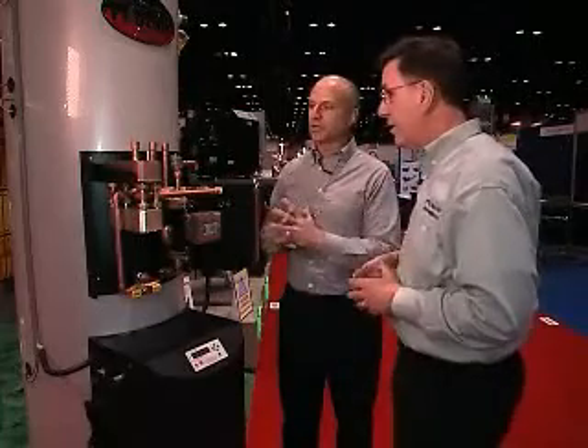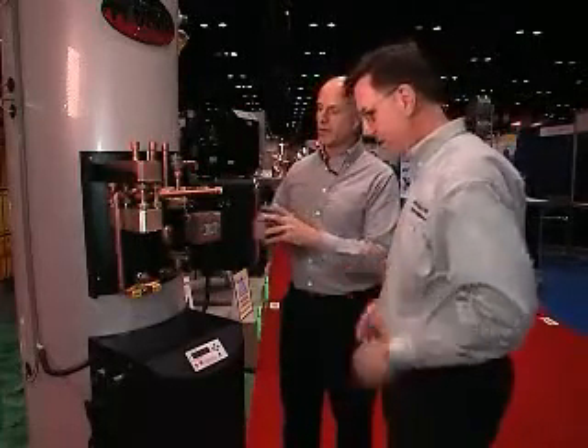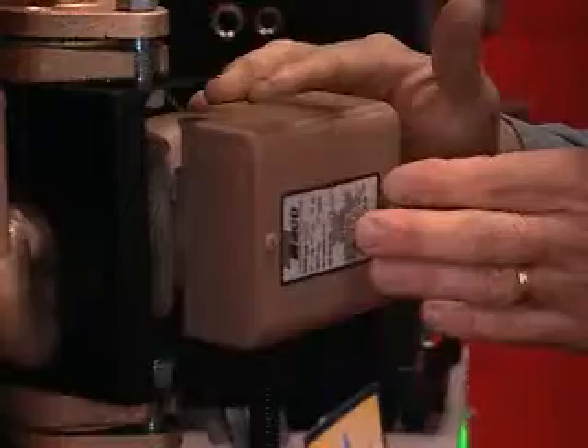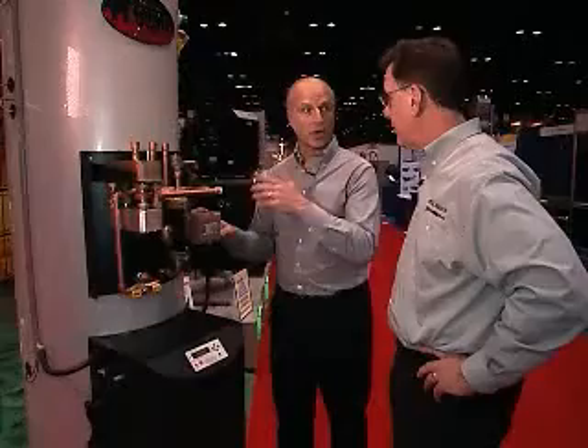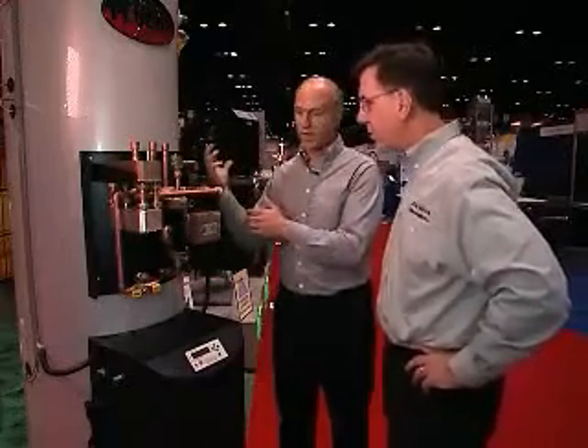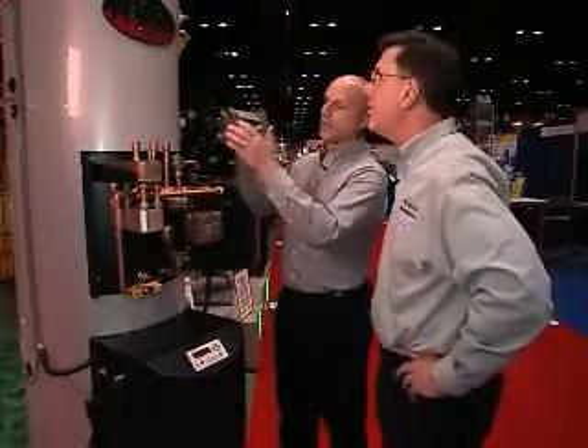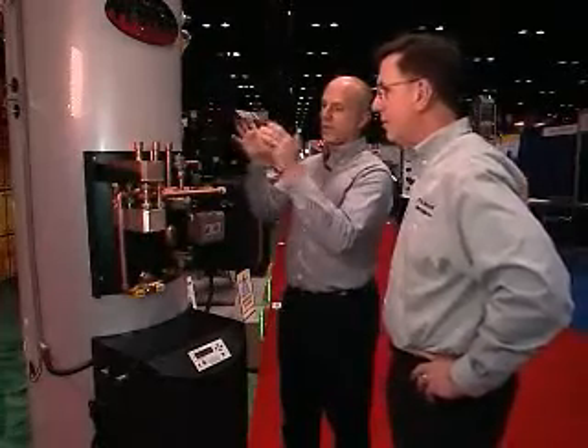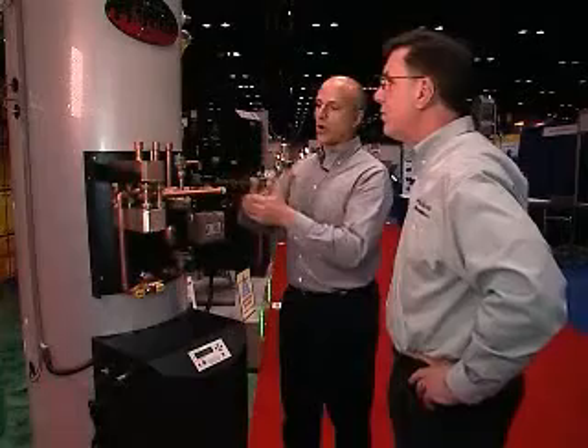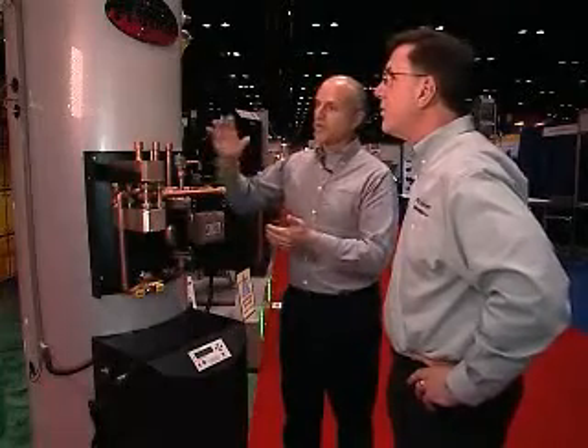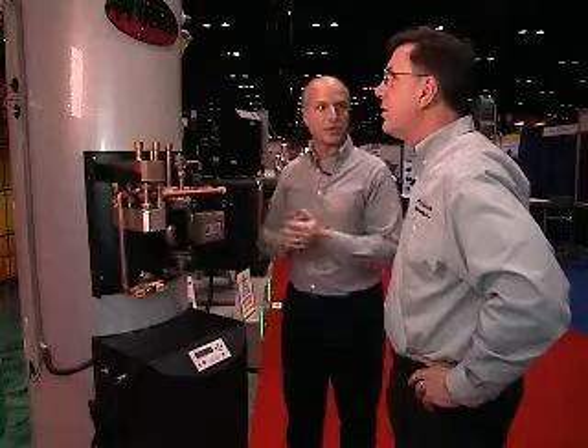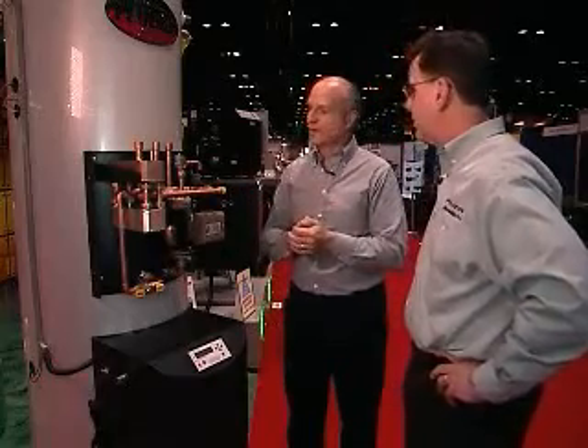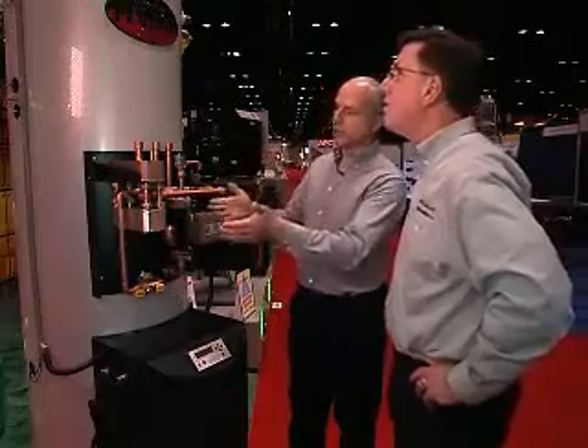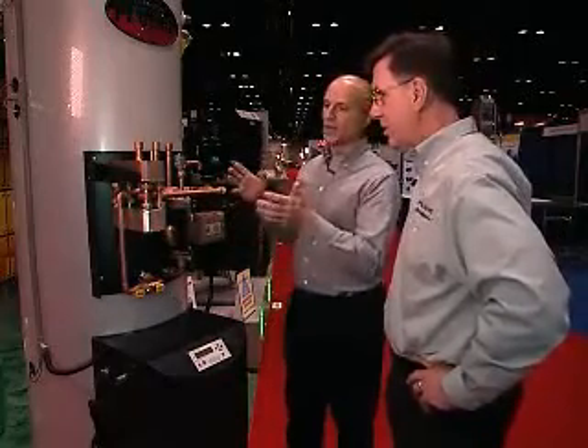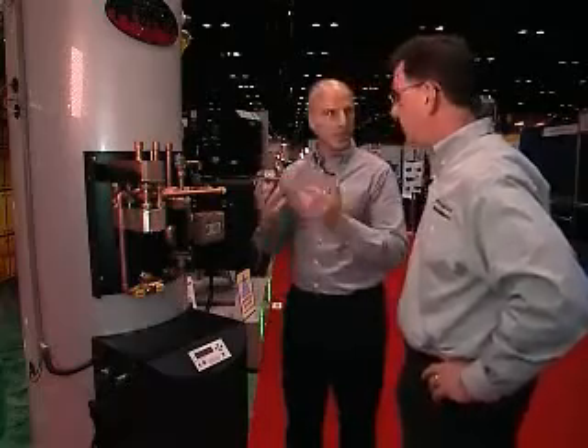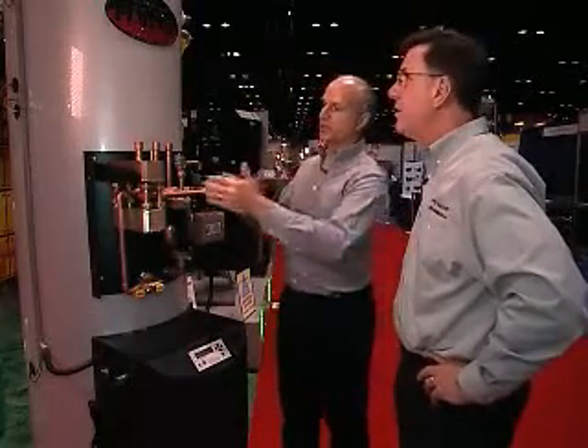Nothing. They're two completely separate systems, and the beautiful part about this is not only do we have less electrical consumption because we're varying the speed of the pump from a 30% duty cycle to 100% depending on the load of the space heating, but we're utilizing the tank, and we're basically resetting the tank temperature to always shoot for the lowest operating temperature for domestic and space heating to increase the overall efficiency of your system. It's that simple. Sounds like a great option for radiant. Oh, definitely. We've pre-plumbed it and pre-wired it, so it takes all that extra piping and things that contractors have to do in a job, and puts it in one small package.